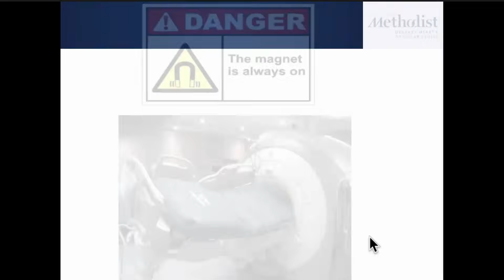So you can have very serious consequences. That's why, from an MRI safety standpoint, there are a few important things we all need to be aware of. One is the safety zone designation for any MRI suite. MRI zone 1 is basically the entrance to the facility. MRI zone 2 is the area where you actually screen the patient for metal safety. That's where you find out: does this patient have a pacemaker or defibrillator? Do they have any shrapnel? Do they have any history of welding or grinding, where they could have little metal shrapnel in their eyes? Because you want to know about every single piece of metal this patient may have. It doesn't mean that if somebody has metal, they can't get an MRI scan, but rather it's important to understand what they've got, and then you can do a risk assessment.